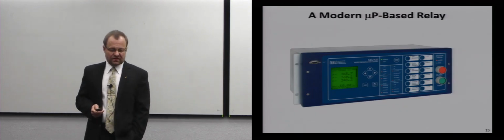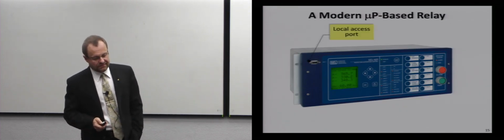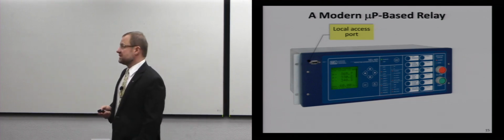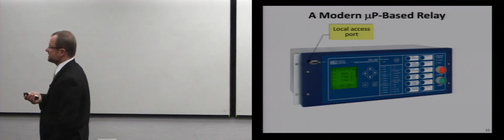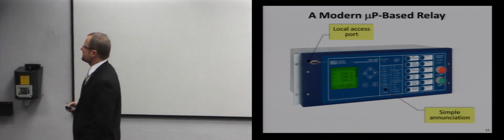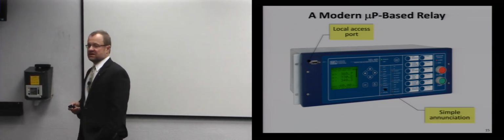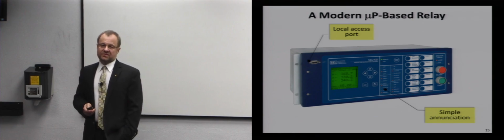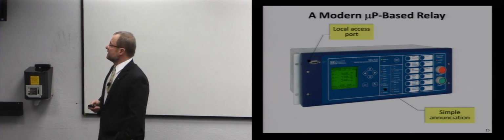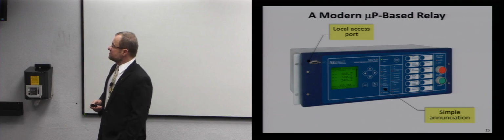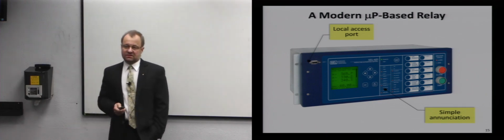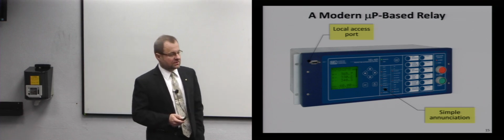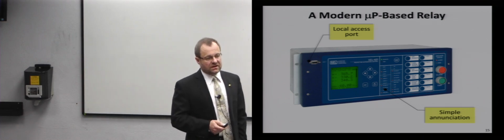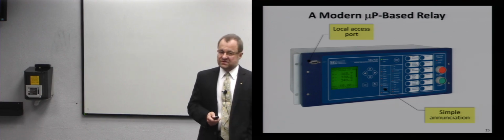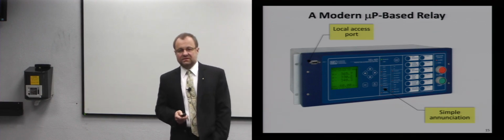So this is a view of a modern microprocessor-based relay. You have a local port. People like to have a local port to just plug in the laptop and interrogate the device. You have simple annunciation telling you that, okay, I tripped from a distance function, or I tripped from an overcurrent function. This seems to be very simple and old-fashioned, but this is required because this is not for PhDs. This is for technicians in a substation. When they are there, tired, and for a specific reason, things need to be very simple.